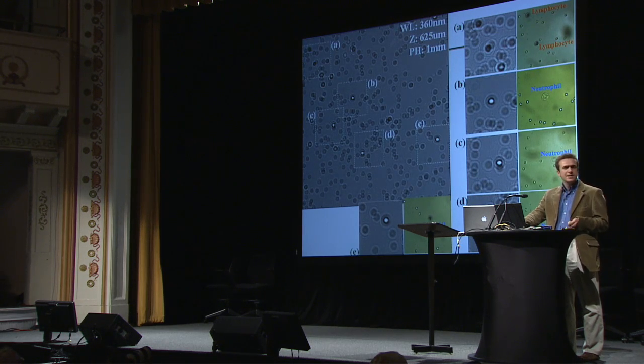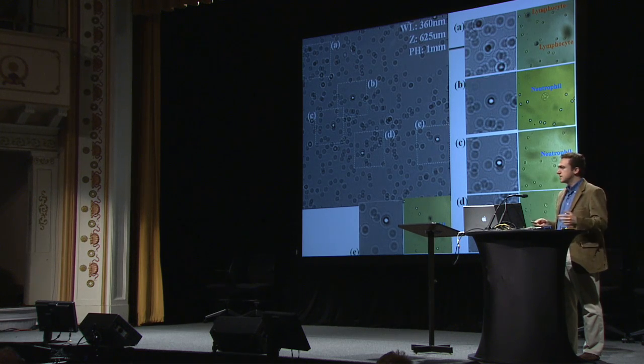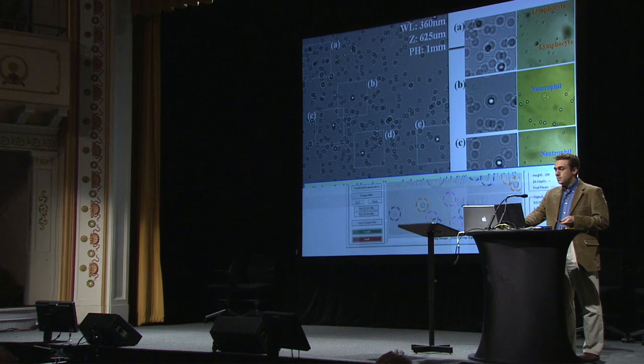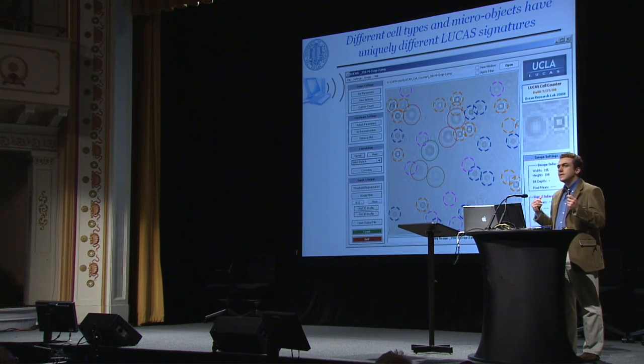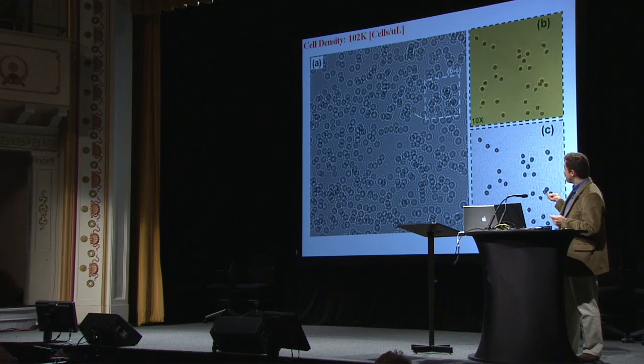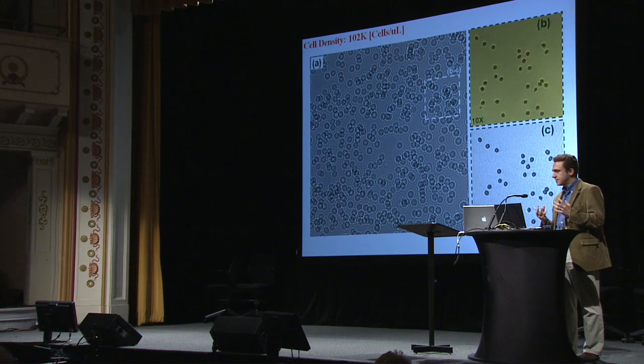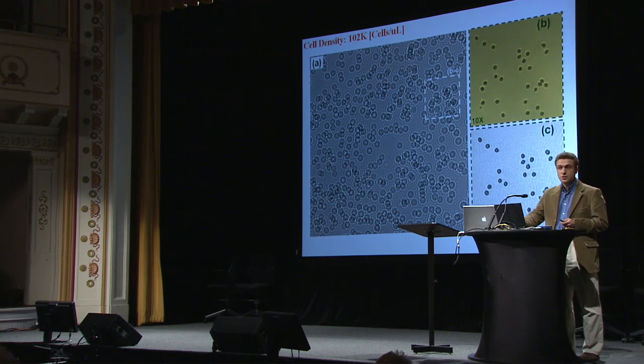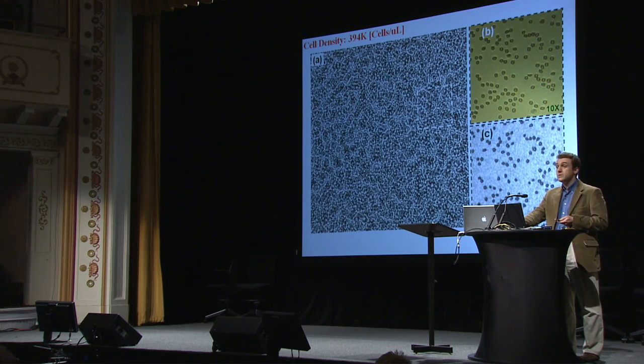These are some examples of whole blood samples that you would be able to image with our devices. What you see mostly are the shadows of red blood cells, because our blood is mostly composed of red blood cells. Every now and then you would see some lymphocytes and neutrophils, which you could count for different purposes. If cell shadows start to overlap in your camera, because these are very nice textures containing holographic information, we have fairly powerful software that can undo this overlap to get the exact image of the cells through digital computation, without the use of any lenses — even with extensive overlap.